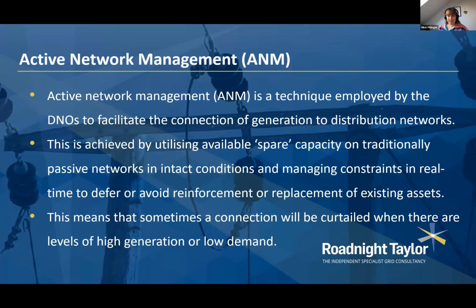We've got a couple of tactics to alleviate this. We've got active network management, which is more of a flexible solution. So instead of just assuming worst case on the network - peak generation and lowest demand - we put various controls onto generators and within the networks to allow people to constrain off their generation at times of peak generation, so they don't have that overloading impact on the grid.